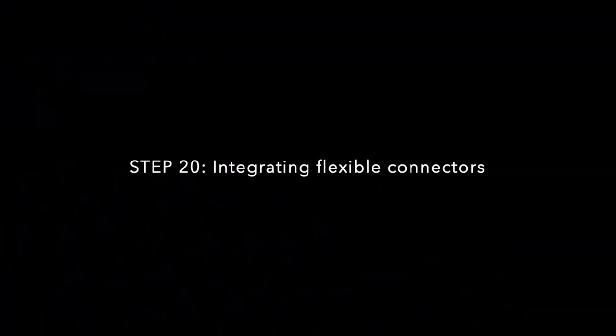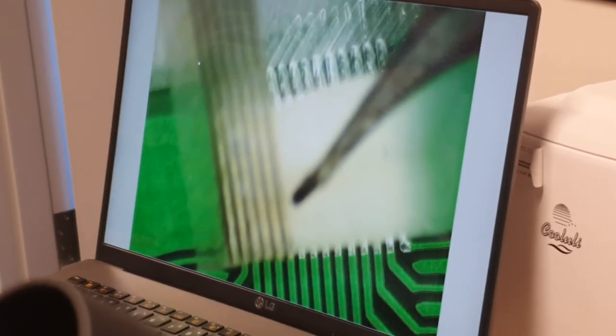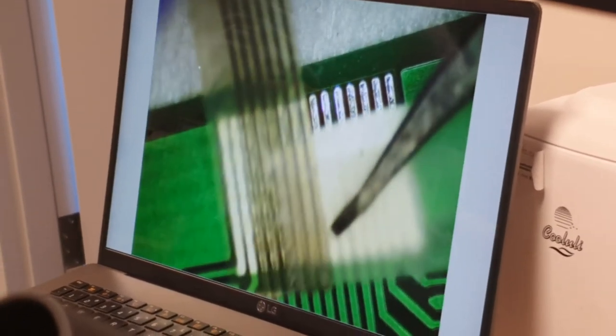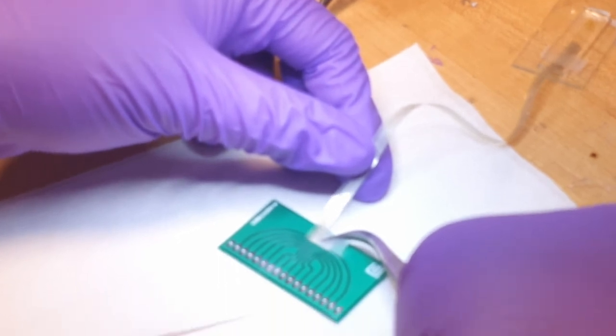We're ready to integrate the electric connections. Under our microscope, we carefully align the flexible ACF cable with the contact pads on the breakout PCB board and apply heat and pressure for adhesion.